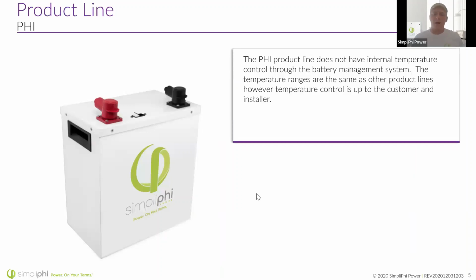One thing to keep in mind, as we discuss several of our products today, is with the Phi battery, as far as low temperatures, you may run into some issues. The Phi battery does not have internal temperature control through the battery management system, so temperature control here is up to both the customer and the installer. You'll want to make sure you're not putting this battery in an environment where it could get below freezing, because if you attempt to charge it below freezing, it will accept the charge and it could damage the battery.